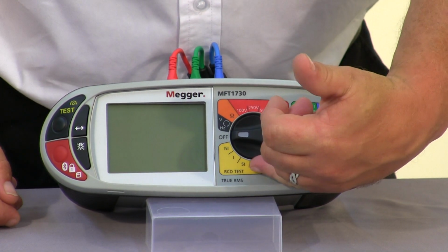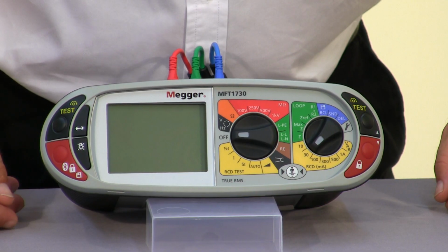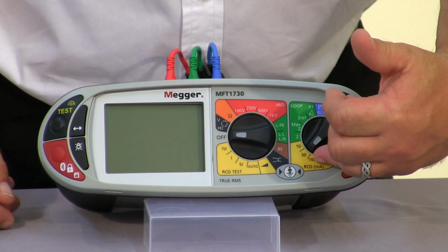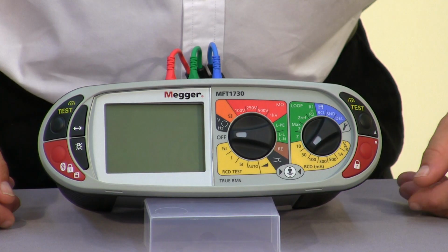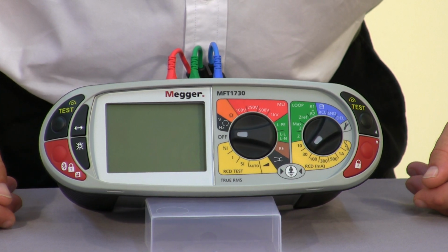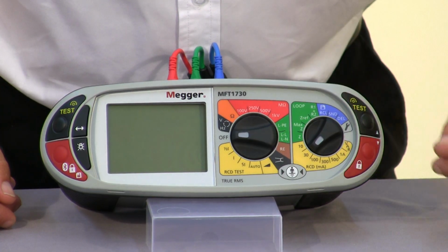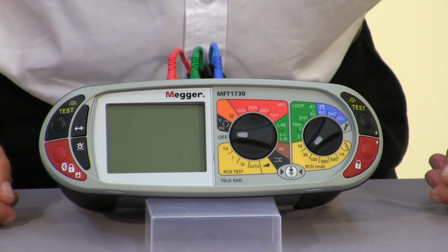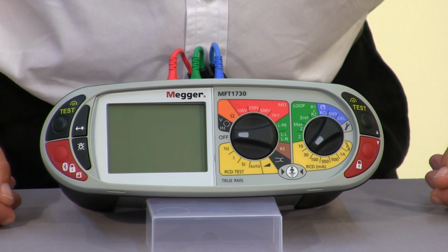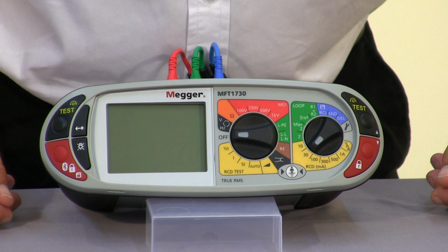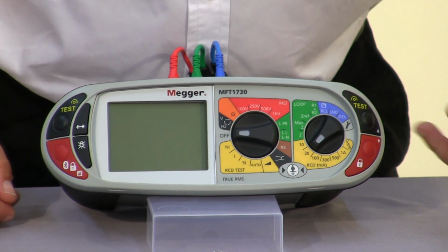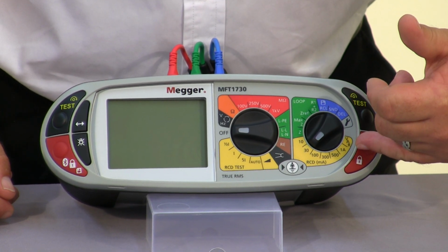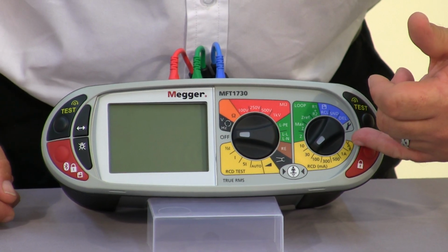We also have the auto test facility, where we can dial up the rated value of the RCD, start the auto test, and it will run through the whole sequence. And then the ramp test, and this is particularly useful when fault finding because it will prove at exactly what value an RCD will operate. We also have our variable RCD, which I shall show you shortly.